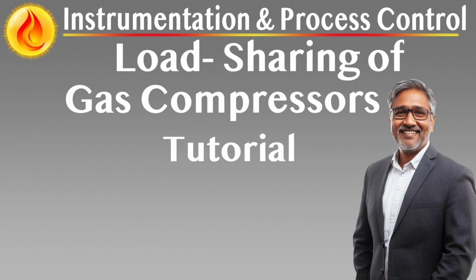Use cases and control flexibility. POC can be configured to respond to any process variable measured by the station controller, not just pressure or flow. This includes suction and discharge pressure, intermediate stage pressure, and flow rate across critical headers. Set point flexibility and response coefficients can be tuned for aggressive override in highly sensitive systems, or gentle correction in slower, stable processes.